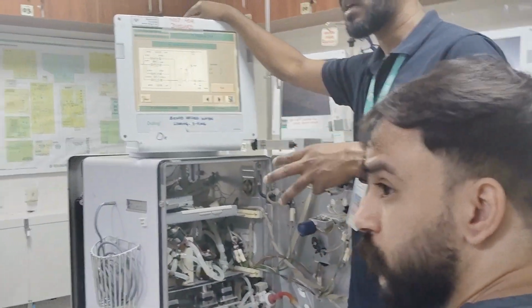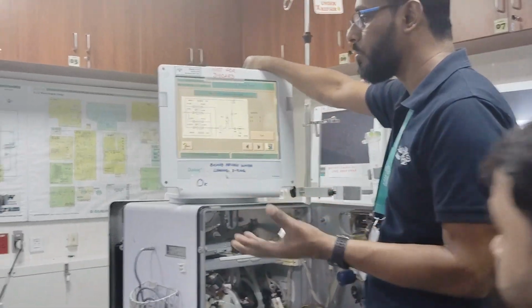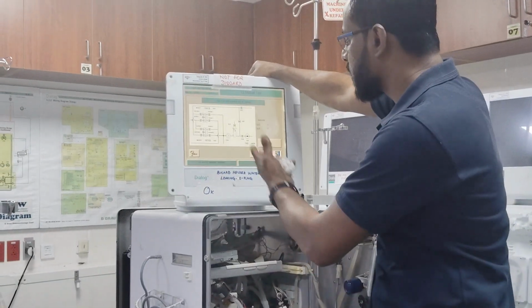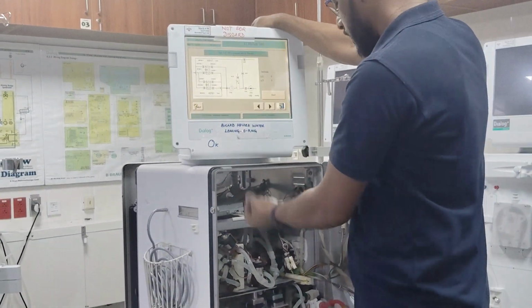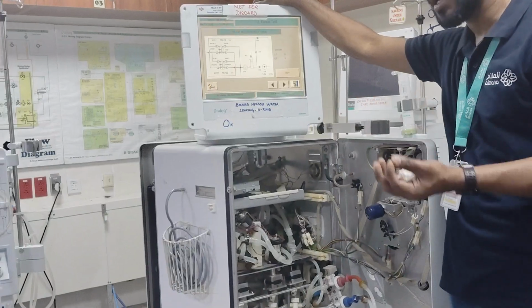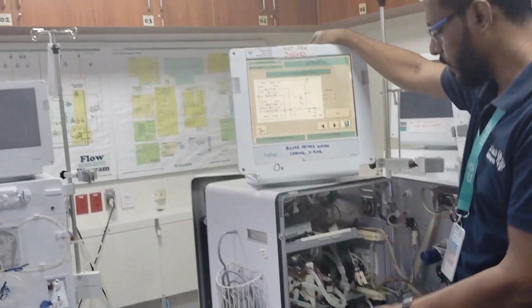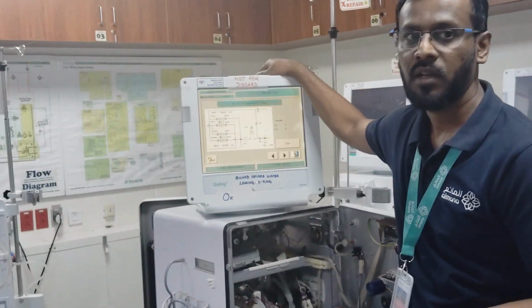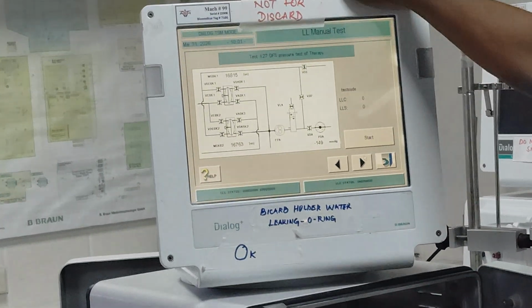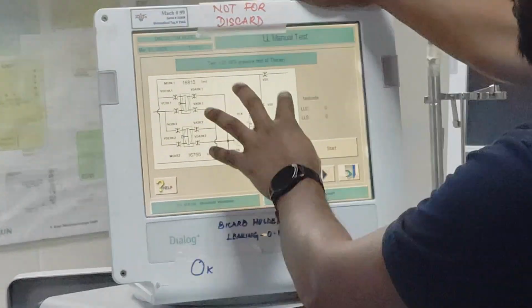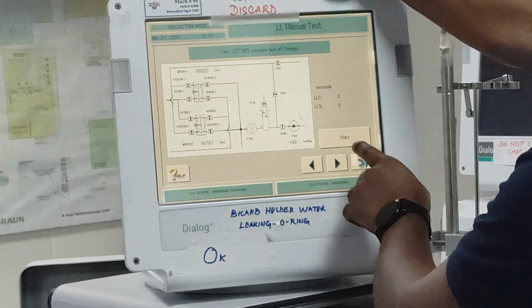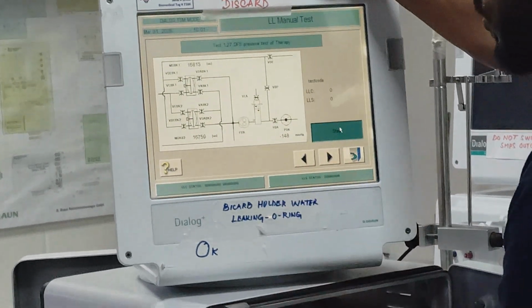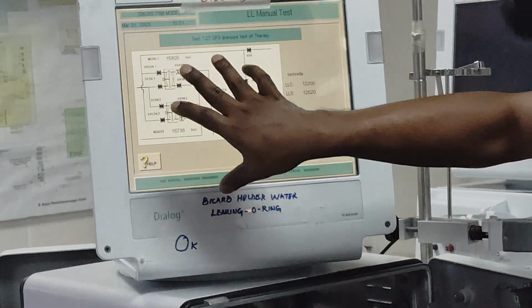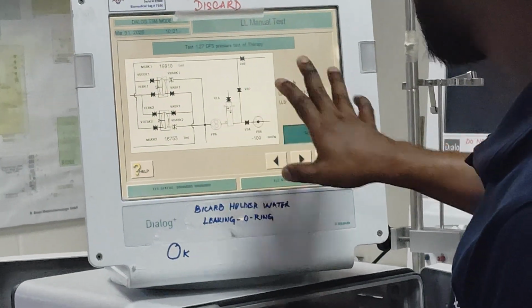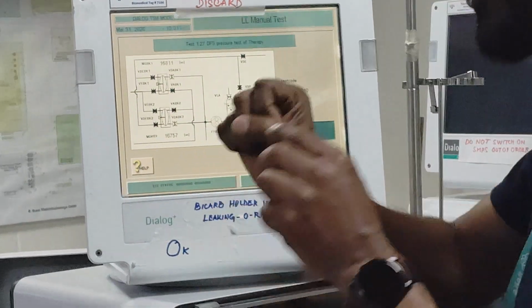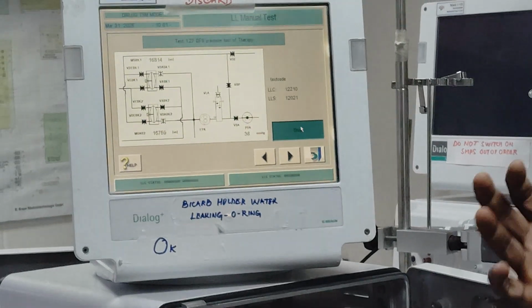Some machines have many issues and will fail the pressure test for many reasons. You cannot tell whether something is leaky or not leaky. There are many reasons for that. If we need to test the machine anywhere, we can get these issues. So here also we can do that testing. Here we are trying to do the test, and it is trying to check all these valves, membranes, and mostly the valves only. It is trying to check whether any valves are leaking or it is okay.